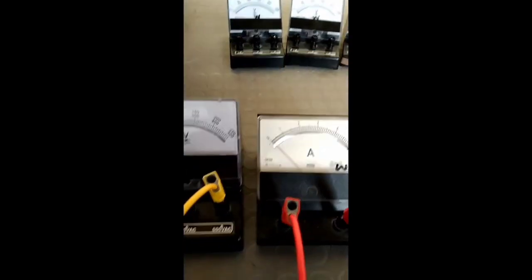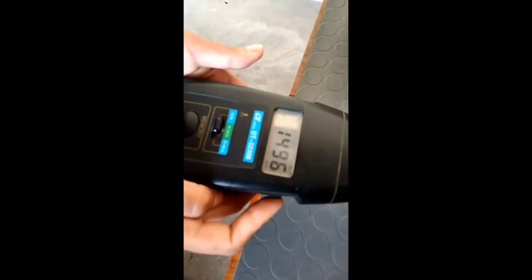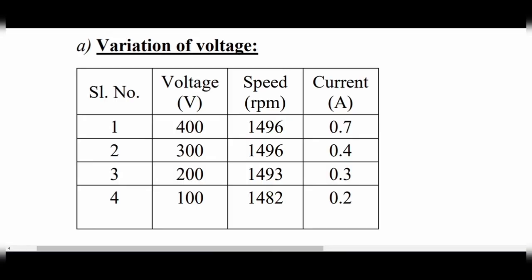In this practical, rated voltage of 400 volts is given and its speed is noted. We are going to decrease the supply voltage and note its RPM. This is the reading of this practical, and you can see that as supply voltage decreases, RPM also decreases.